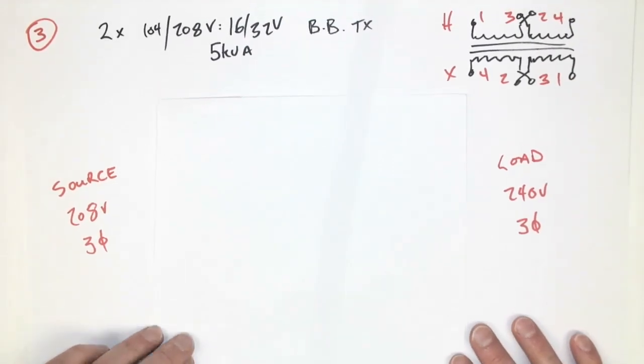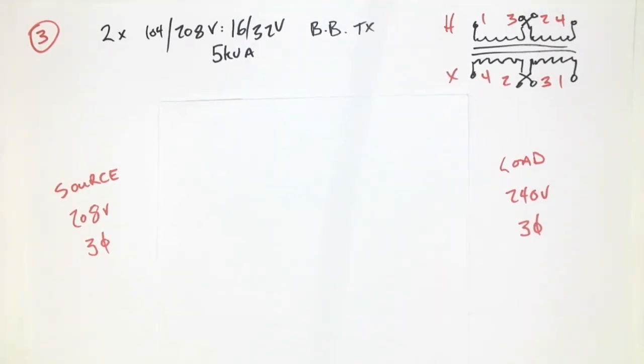This time what we're going to do is connect a delta, open delta. So open delta requires only 2 auto transformers, and because it's connected in delta, we don't need phase values. All we need is the line voltage values. And I would say for most often, it's actually more common to see this type of connection, and it's actually easier to calculate. All right, so first thing we need to do, 208 volt source, 240 volt load. Let's sketch out our 2 individual transformers with all their windings and in an open delta configuration. So there we have the open delta configuration.